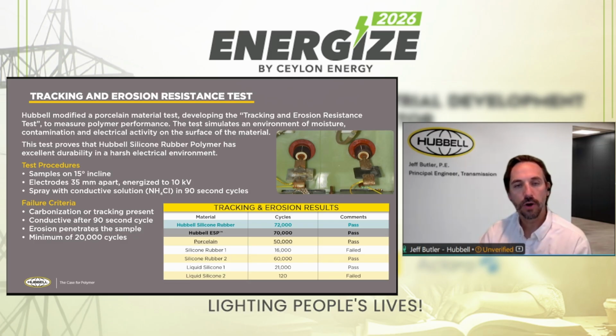And now the cycles are, you're taking a plaque, you're placing it between two electrodes that are energized at 10 kV, 35 millimeters apart, and then you're cycling a conductive solution being sprayed on it every 90 seconds. And so that is a cycle. So you want it to at least pass 20,000 cycles. And you can see that for porcelain, 50,000 is the target, and the two Hubbell materials exceeded the porcelain. The silicone rubber 2, as well, did exceed the porcelain minimum. And then you can see the ranges of the others.